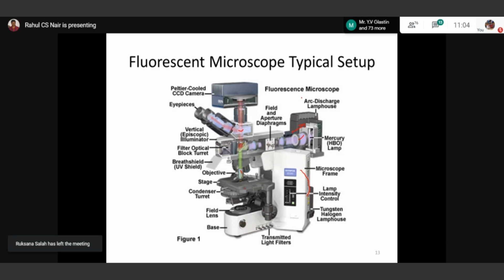Now, to explore the filters in more detail, you see the filter cube. This is the filter cube I presented earlier, and it has emission characteristics on the right side. You can see that the excitation light, the red curve, is band limited, but the emission filter passes a different range. That is the characteristic of the filter, and these filter cubes are mounted in a special assembly on the microscope, so that you can see the teeth on the surface. Micro positioners or stepper motors are moving these filters. Even though you can control it manually, usually these types of microscopes are driven from software. There are also linear slide filters like this, and you can push or pull them so that the appropriate filter comes into the light path.